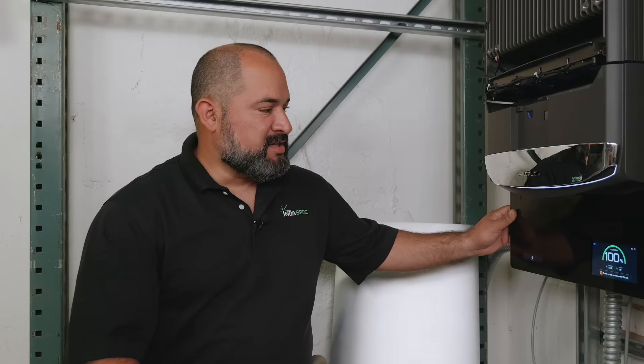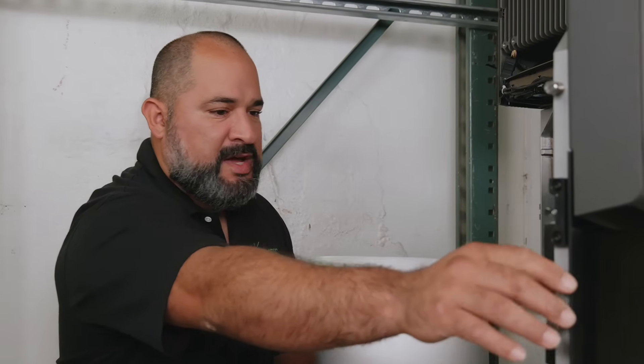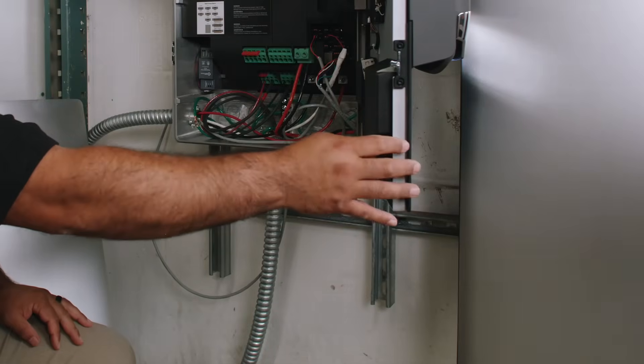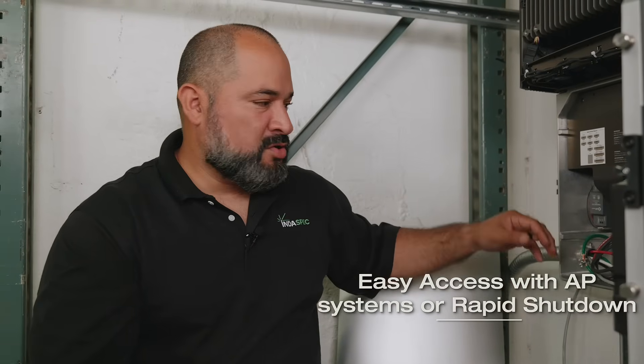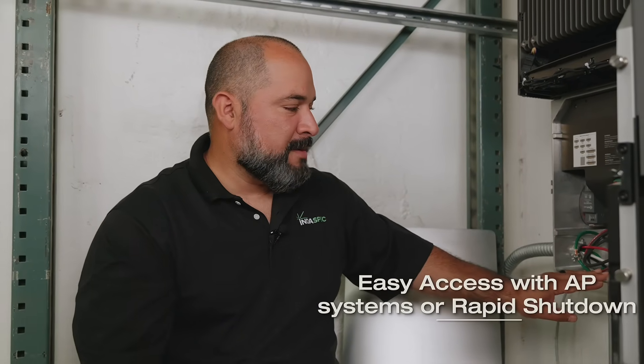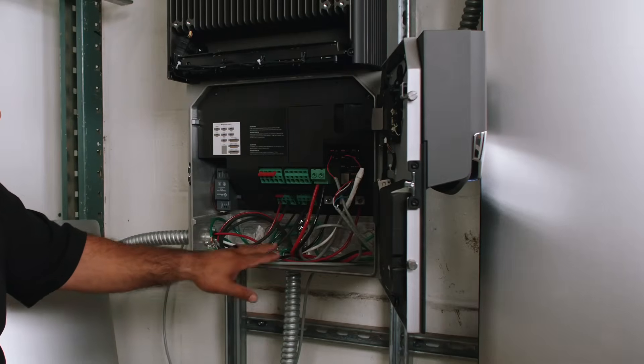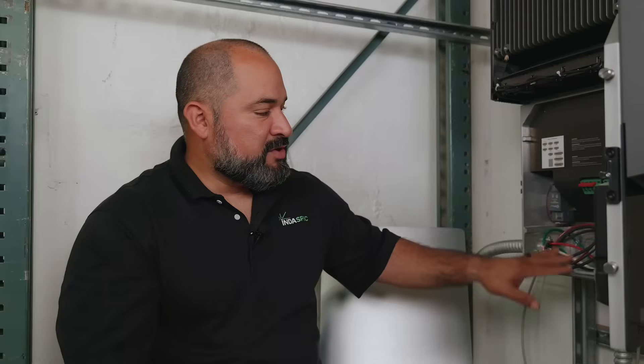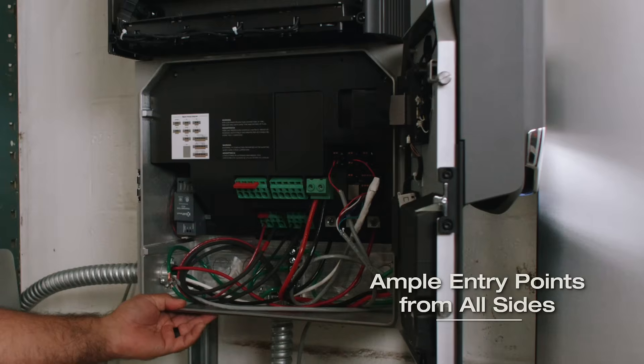We're going to take a look inside the EcoFlow inverter. It is a very easy to open enclosure with two spring-loaded locking bolts. Once exposed, we have full access to the wiring compartment. We have a rapid shutdown transmitter already pre-configured, with easy access for either AP Systems or Tigo rapid shutdown. We have our eight DC MPPTs, battery terminals, and the spacing between terminals allows you to land wires very easily, with entry points from the bottom, side, and back.